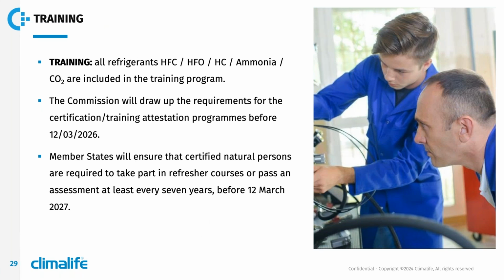To do this, training on all HFC, HFO, HC, ammonia, and CO2 refrigerants becomes mandatory and is included in the training program. The European Commission will establish the requirements for certification and training programs before the 12th of March 2026. Member states shall ensure the certified natural persons are required to attend refresher courses and undergo evaluation at least every 7 years.